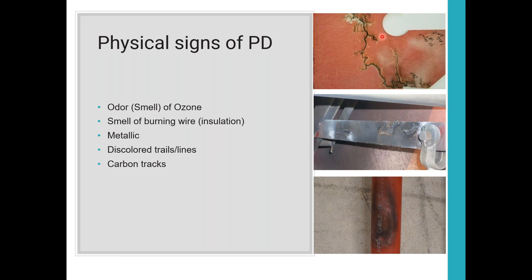This top picture here is a piece of an insulator board that was in a lineup of switchgear. And you had one piece down here, they labeled it ground, that was touching metal. Another piece up here near the top of this picture that was very close to a conductor. And over time, partial discharge eroded and caused this carbon trail to occur in this barrier board. Now, if you were to hold this up, these white areas, you could see light through, extremely broken down.